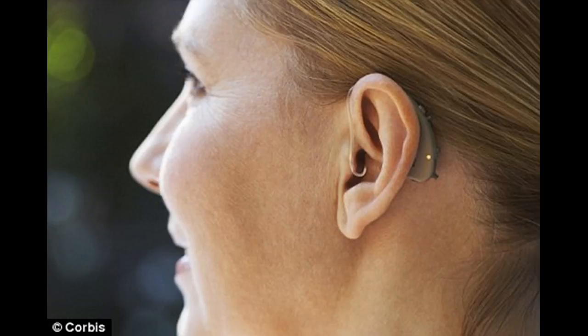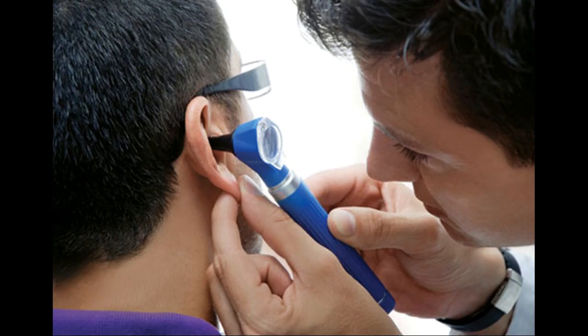Bone conduction hearing aids are recommended for people with conductive or mixed hearing loss who can't wear a more conventional type of hearing aid. Bone conduction hearing aids vibrate in response to the sounds going into the microphone. They can also sometimes help people with no hearing in one ear and normal or mild hearing loss in the other ear. The part of the hearing aid that vibrates is held against the bone behind the ear by a headband. The vibrations pass through the mastoid bone to the cochlea and are converted into sound in the usual way. They can be very effective, but can be uncomfortable to wear for long periods.